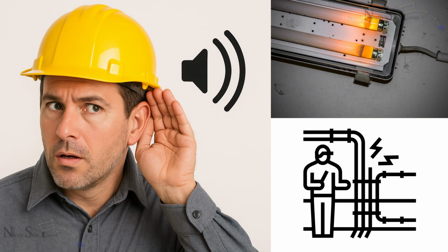How does the substation sound? Is there excessive electrical noise or vibration, buzzing or hissing? That is a telltale sign of loose hardware, corona, or leakage current. Do the lights flicker? Are there records of breakers nuisance tripping? Are there unexplained failures of sensitive electrical components in the facility? These things indicate various electrical problems.